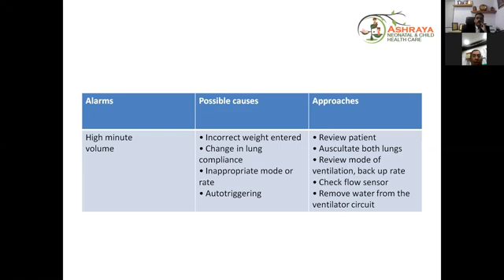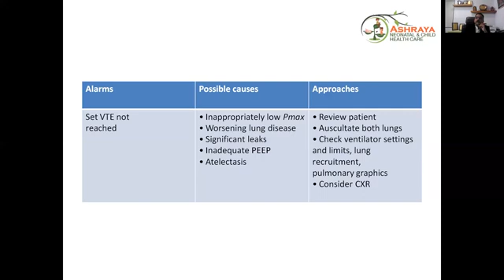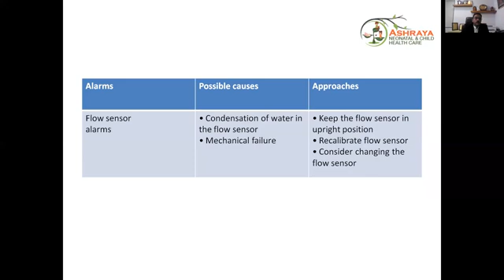When the set tidal volume is not reached, an inappropriately low Pmax and worsening lung disease could be causes, as well as significant leaks, inadequate PEEP, and atelectasis. These are the common causes we can see, and the approach can be: review the patient again, auscultate both lungs, check ventilator settings and limits, lung recruitment, pulmonary graphics, and consider a chest X-ray. Flow sensor alarms: condensation of water in the flow sensor, and there could be a mechanical failure. The approach should be to keep the flow sensor in an upright position, recalibrate it, and consider changing the flow sensor.